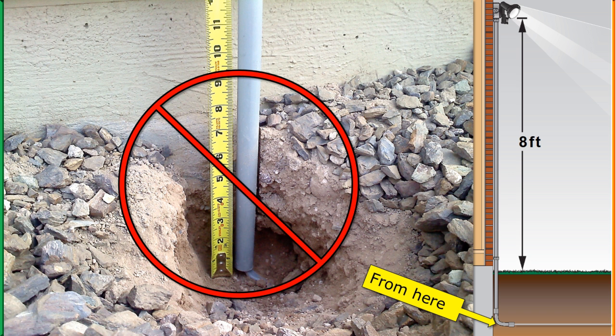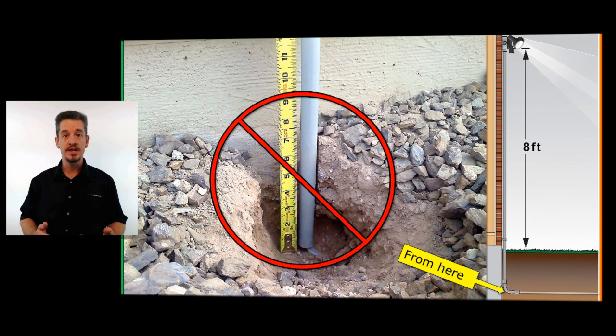And then the backfill material, that's a little bit questionable. Look at those sharp rocks. They're not big sharp rocks, but they are sharp rocks. Wouldn't be a bad idea to go ahead and put down some sand shading over the top of that cable or maybe some clean backfill before you start dropping rocks in. Thanks for watching. Have a good day and be safe when you're digging underground.